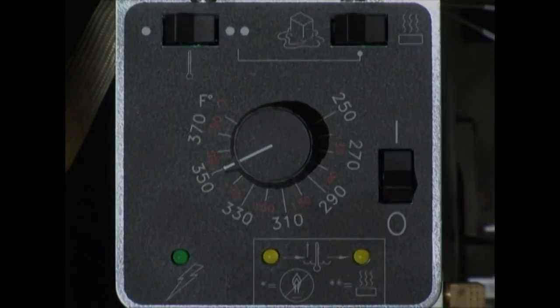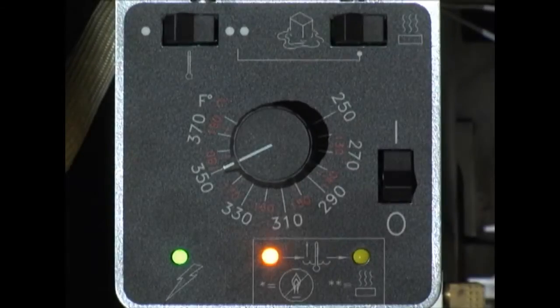control back on. For high limit trips or heat failure codes, this control monitors the appliance response to heat demand signals. Under normal conditions, the heat feedback indicator follows the heat demand indicator. When the appliance fails to respond, the heat feedback indicator will remain off. Typical causes are: high limit device is tripped and needs to be reset. On gas appliances, a substandard pilot flame or ignition module problem may be indicated, and for electric appliances, an open line fuse may be indicated.